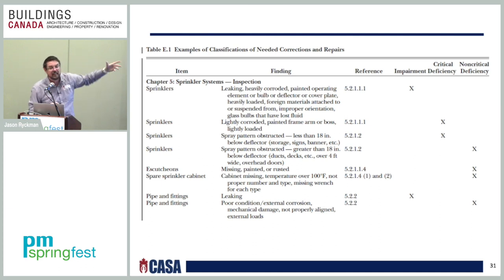So ultimately, if you see any of that, and I bet you're asking the question, what does heavily loaded mean? Heavily loaded is basically when you see a ton of dust particles on the sprinkler head. I'm sure you've seen it before. It's nasty stuff. There's ways to clean that, preferably with compressed air from a far distance so you don't disrupt the element. But that would be an example of an impairment. And that's where this becomes very subjective, and a judgment call has to be made by the inspector.